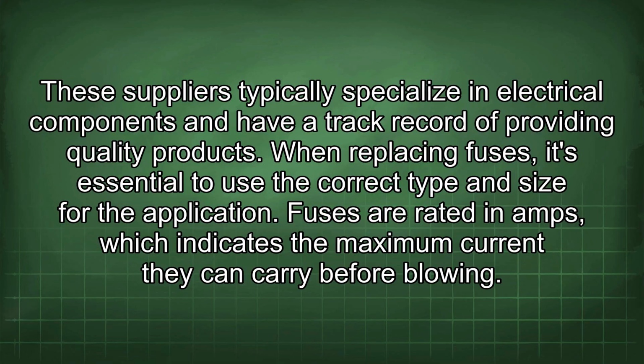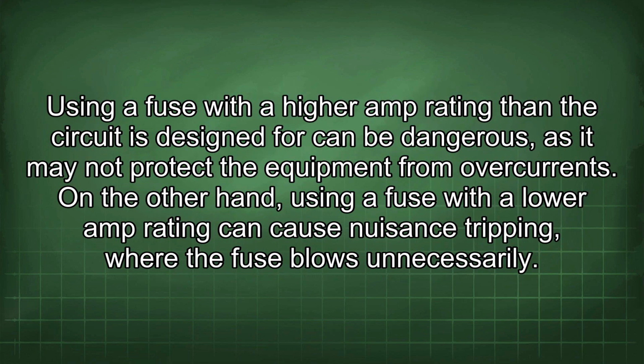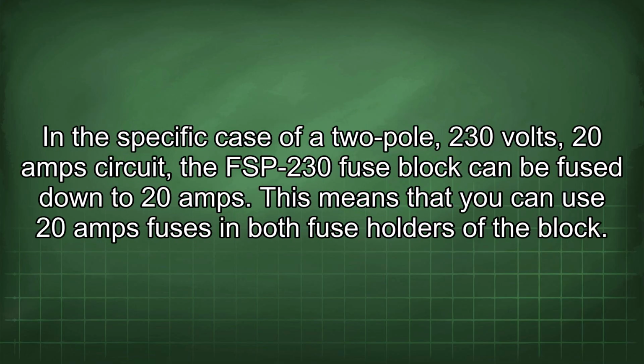When replacing fuses, it's essential to use the correct type and size for the application. Fuses are rated in amps, which indicates the maximum current they can carry before blowing. Using a fuse with a higher amp rating than the circuit is designed for can be dangerous, as it may not protect the equipment from overcurrents. On the other hand, using a fuse with a lower amp rating can cause nuisance tripping, where the fuse blows unnecessarily. In the specific case of a 2-pole, 230 volt, 20 amp circuit, the FSP-230 fuse block can be fused down to 20 amps. This means that you can use 20 amp fuses in both fuse holders of the block.